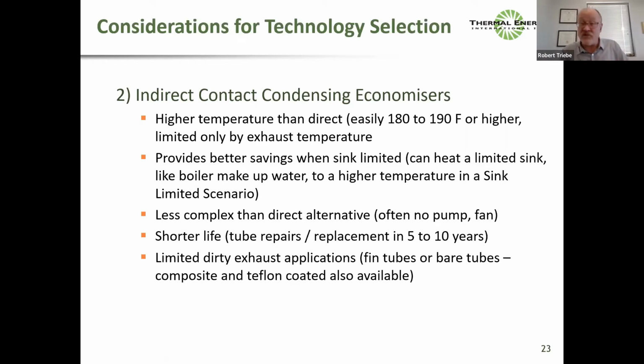However, the life is absolutely shorter, without question, because when you get a droplet on the outside of a tube, even if the tube is stainless steel, that droplet is an acidic droplet. You get a dielectric effect, you get an acidic effect. And so with indirect units, within 5 to 10 years, you're certainly going to be doing tube repairs and replacements. And in addition, it's got limited dirty exhaust application. Direct contact, for example, works beautifully on diesel without problem. Indirect contact, diesel has too much sulfur, and you're gonna ruin those tubes, not in 5 to 10 years, but in 5 to 10 months.